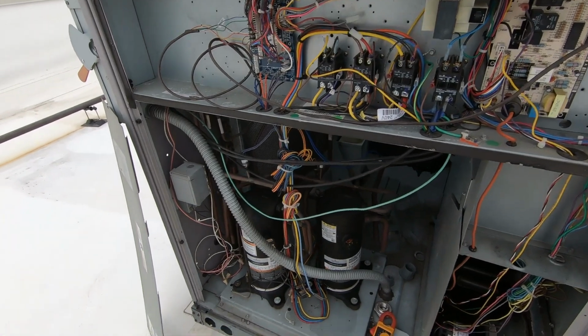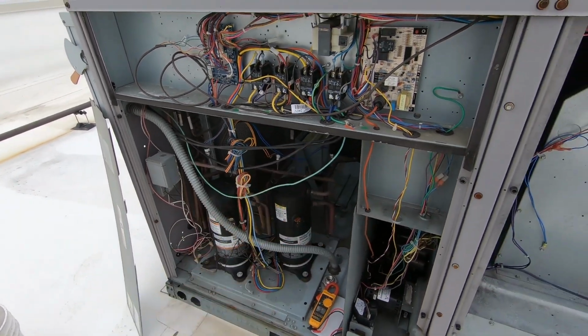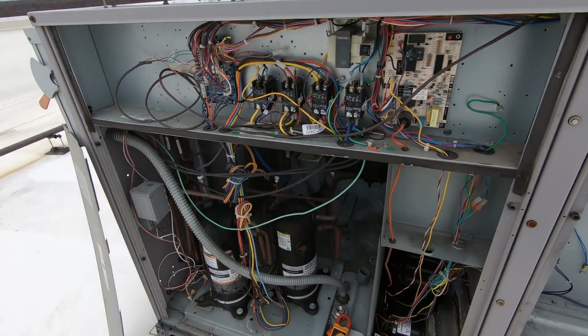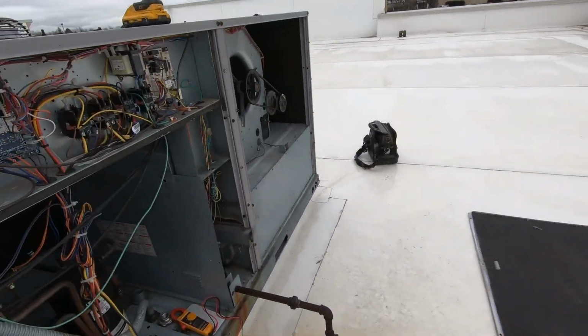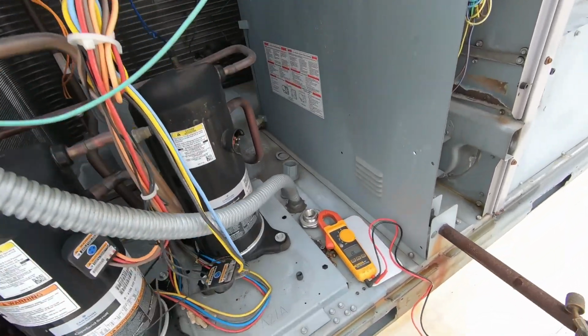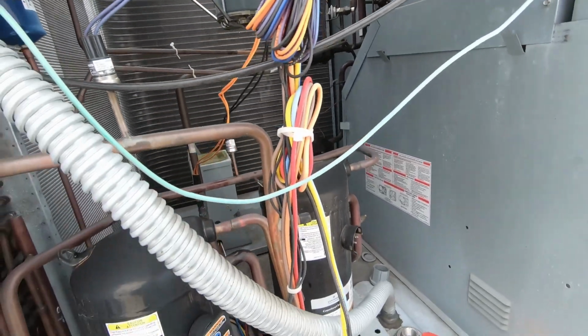I'm going to write up that things have been rewired, plugs have been pulled. Maybe it's out of refrigerant. But that would prevent the first stage compressor from coming on unless they bypass the low pressure switch.